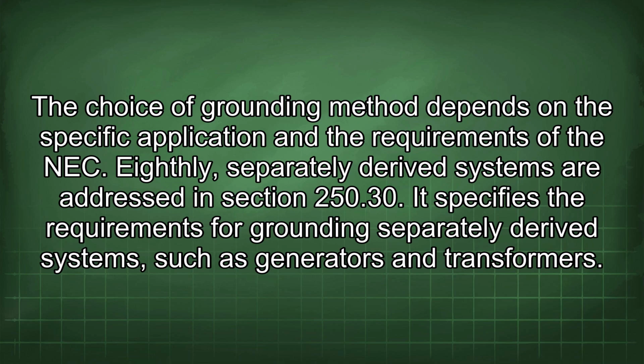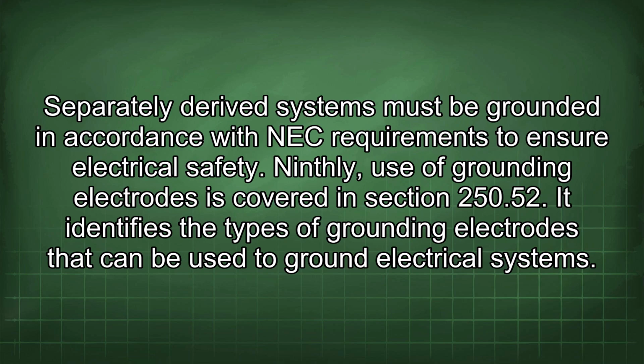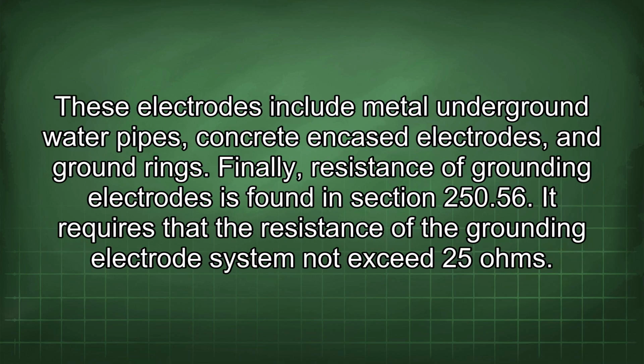Eighthly, separately derived systems are addressed in Section 250.30. It specifies the requirements for grounding separately derived systems, such as generators and transformers. Separately derived systems must be grounded in accordance with NEC requirements to ensure electrical safety. Ninthly, use of grounding electrodes is covered in Section 250.52. It identifies the types of grounding electrodes that can be used to ground electrical systems. These electrodes include metal underground water pipes, concrete encased electrodes, and ground rings.